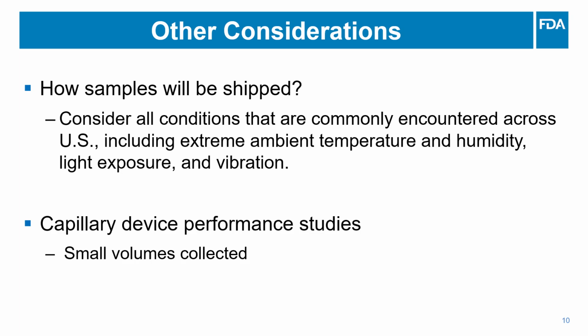Whole blood is highly sensitive to temperature fluctuations. Therefore, shipping stability studies should evaluate the device function and sample quality after the device is shipped as intended and exposed to all the extreme environmental conditions that are possible during this process. The study should simulate conditions that are commonly encountered across the United States, including ambient temperature and humidity, extreme cold, extreme heat, extreme humidity, light exposure if intended for measuring photosensitive analytes, and vibration that may lead to device failure, like sample leaks.